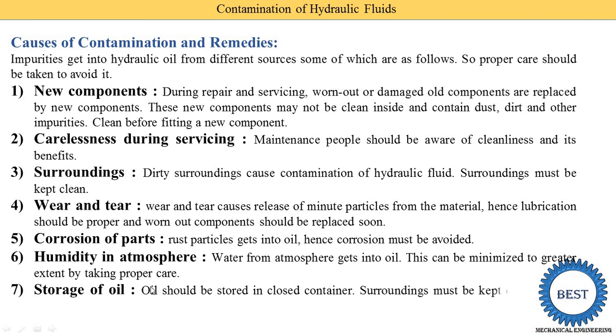The last cause is improper storage of oil. Oil should be stored in a closed container. If stored in an open container, the oil absorbs moisture from the atmosphere, which can convert into water inside components due to different pressures and temperatures. Also, oils of different grades must never be mixed — only one specific grade of hydraulic oil should be used in the hydraulic system.